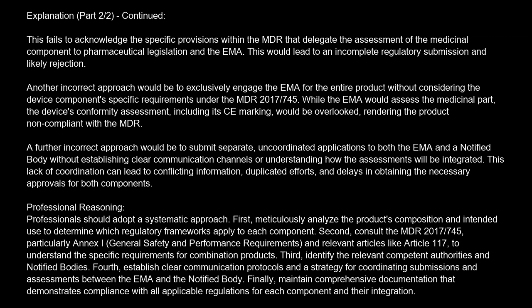Another incorrect approach would be to exclusively engage the EMA for the entire product, without considering the device component's specific requirements under the MDR 2017/745. While the EMA would assess the medicinal part, the device's conformity assessment, including its CE marking, would be overlooked, rendering the product non-compliant with the MDR.